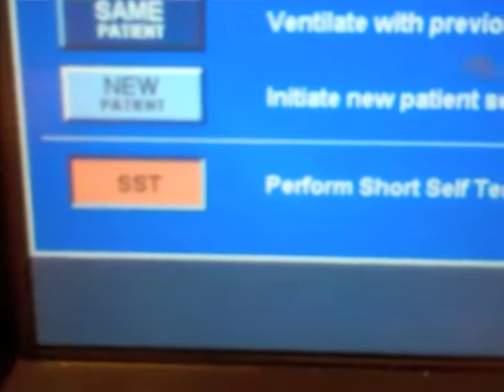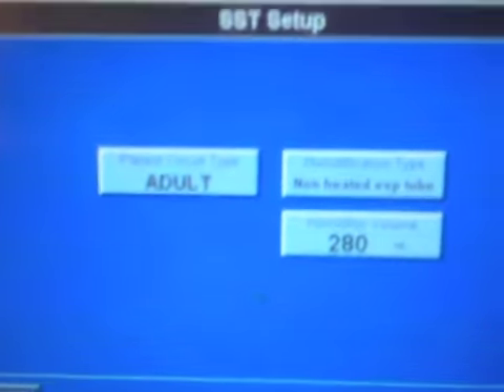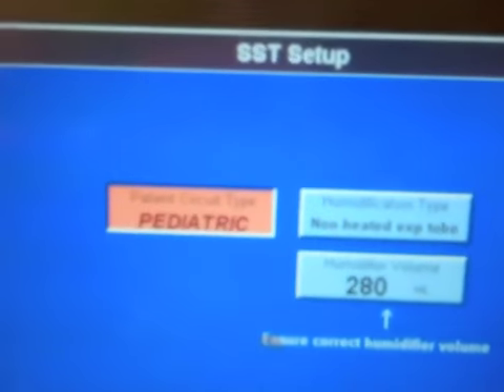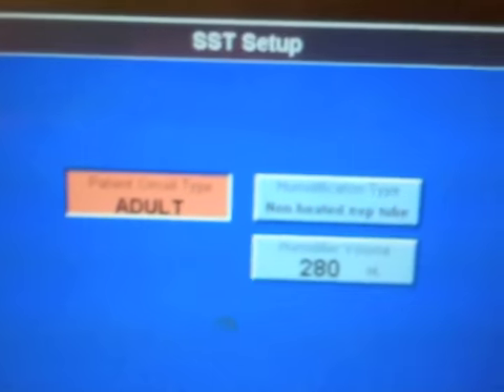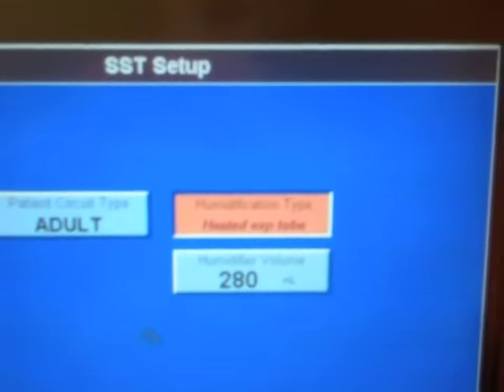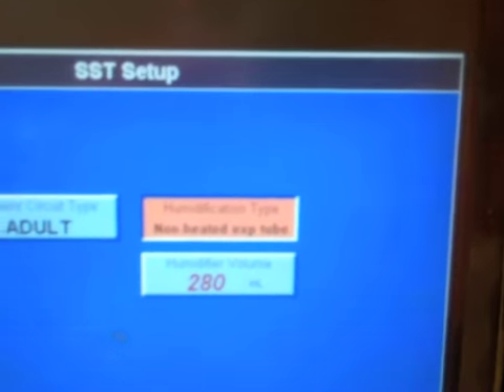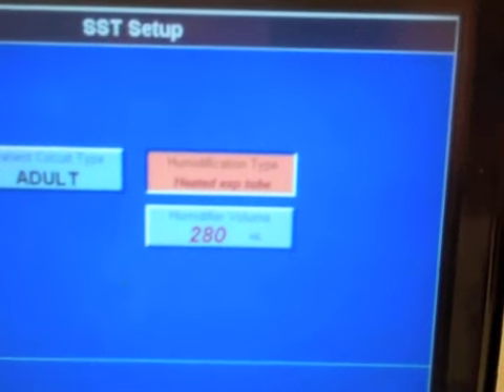So you push this, and you've got to go down to the side and push this test button. It will time out on you, so make sure you do that relatively quickly. What you can do now is input your circuit. I can do adult, peds, or neo. This is an adult circuit. I can choose either heated or HME. This is a heated with a humidifier, so we'll choose this.